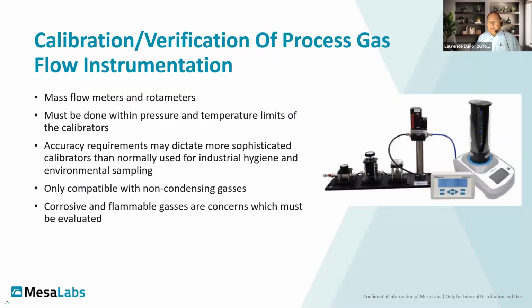For process control, you sometimes have extremely high precision, high accuracy devices that are beyond the capabilities of our typical industrial hygiene and environmental equipment. So if you get an instruction or commission to do this, you need to make sure that your calibrators are suitable for the task at hand. Again, can't use this in applications with condensing gases. Sometimes it'll be corrosive and flammable gases. These are concerns that have to be addressed case by case.